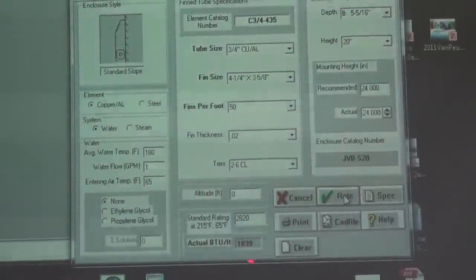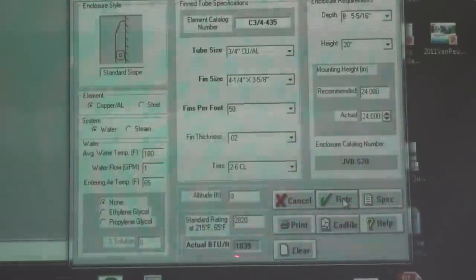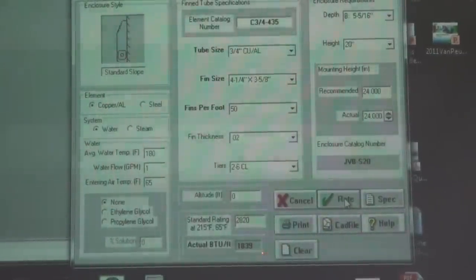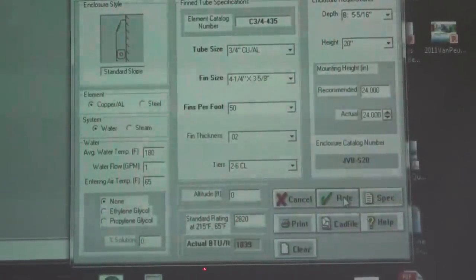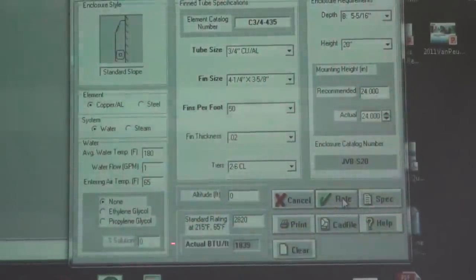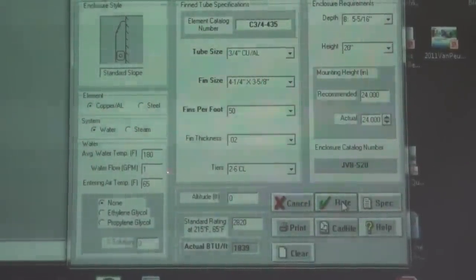Now this is an iterative process. You have to use the energy equation. If you have 10 feet, you have to take this 1839 times 10, and you have to divide it by, in this case since we have no glycol, 500 and your GPM of 1, to figure out what the delta T is.